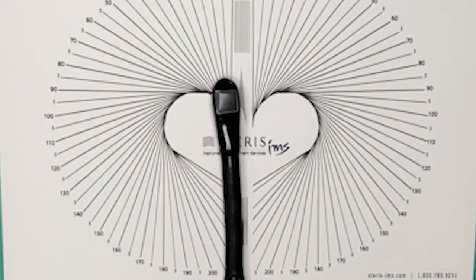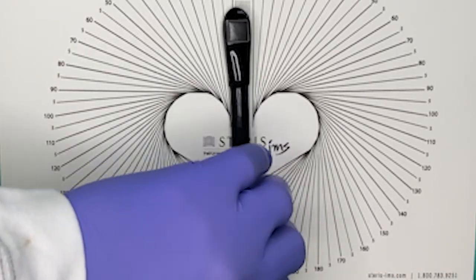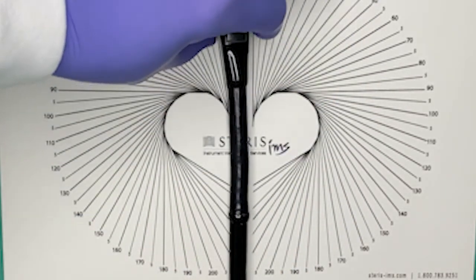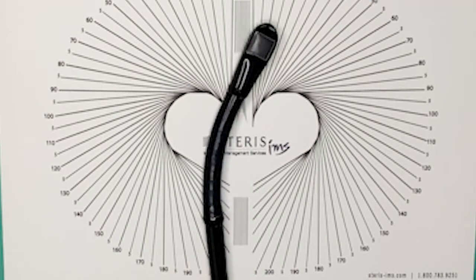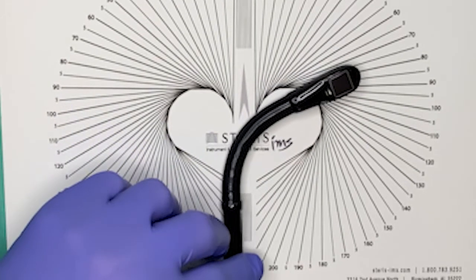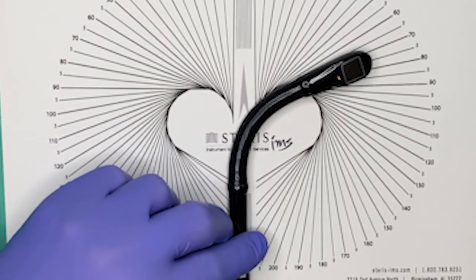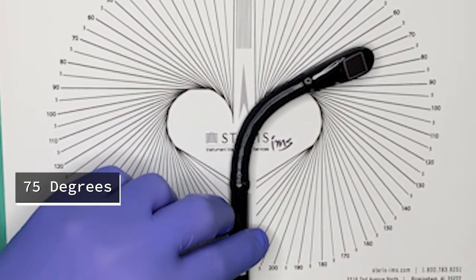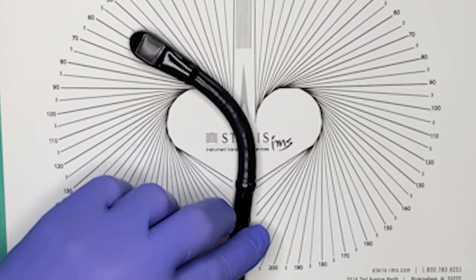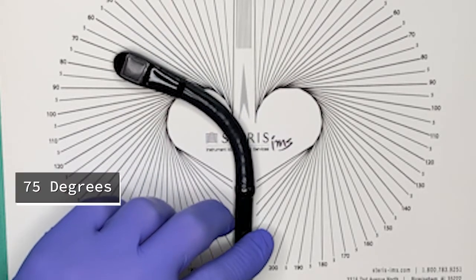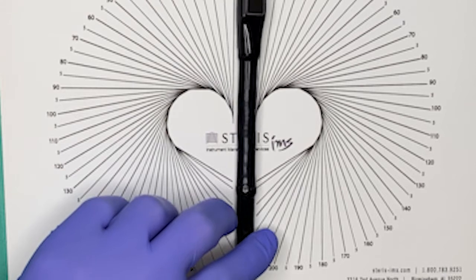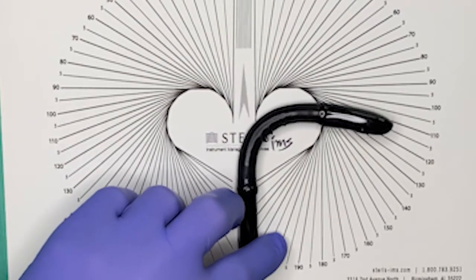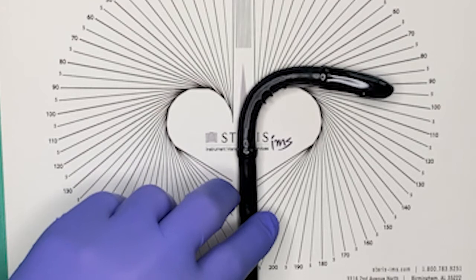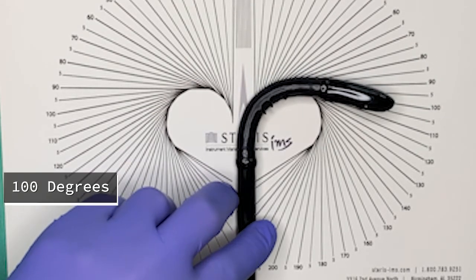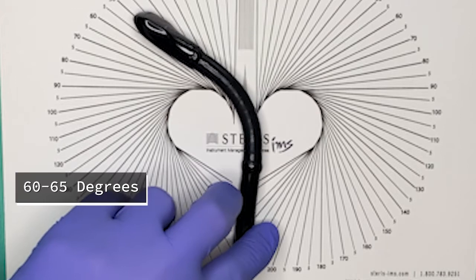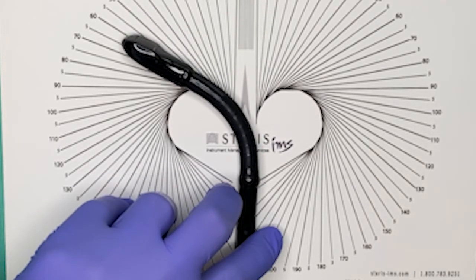For this next step, you'll need the angulation chart to measure the range of motion in each direction. Initial alignment of the chart to the probe is crucial for an accurate measurement. Place the chart under the distal tip and bending section so that you can see the insertion tube is parallel to the center lines on the chart. Measure the maximum range of motion by angulating the probe completely in one direction, noting the maximum. Compare the center of the distal tip to the angle line most parallel on the chart. Measure within plus or minus 5 degrees.